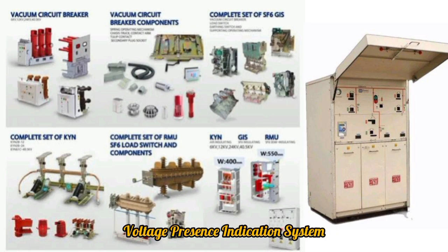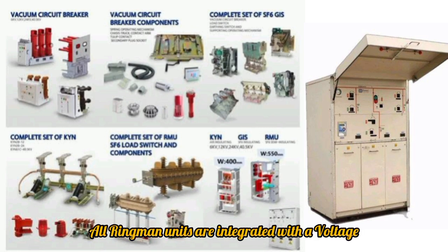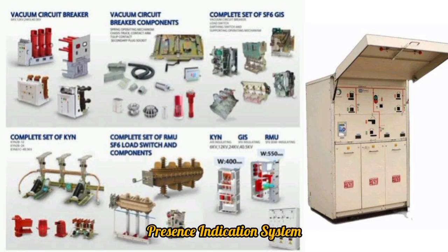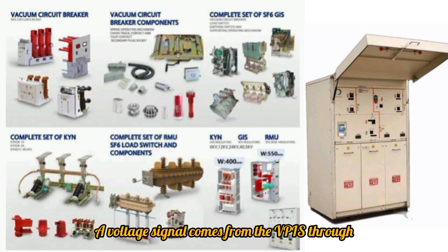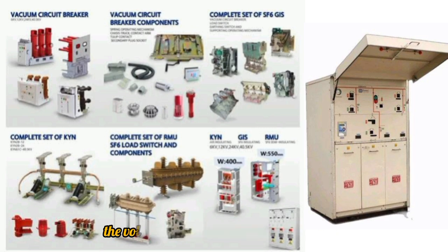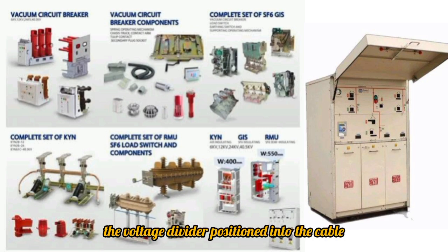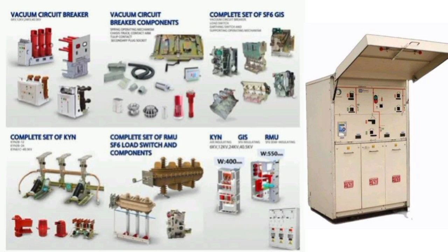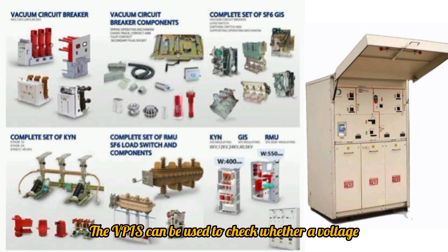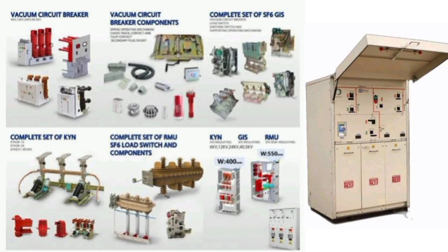Voltage presence indication system. All ring main units are integrated with a voltage presence indication system. A voltage signal comes from the VPIS through the voltage divider positioned in the cable entrance bushings. The VPIS can be used to check whether a voltage is present across the cables.